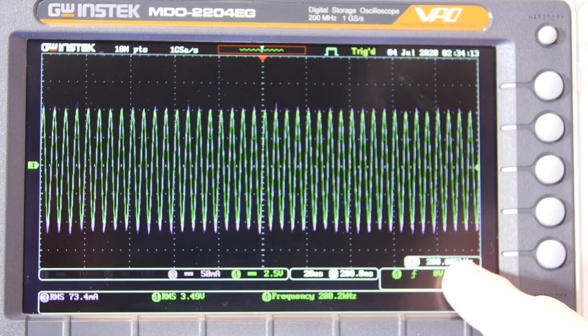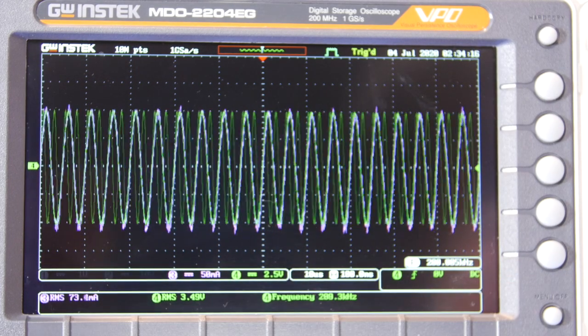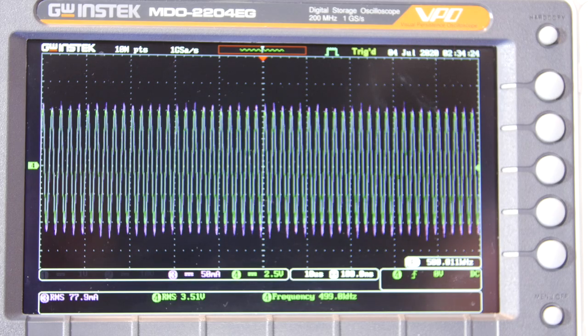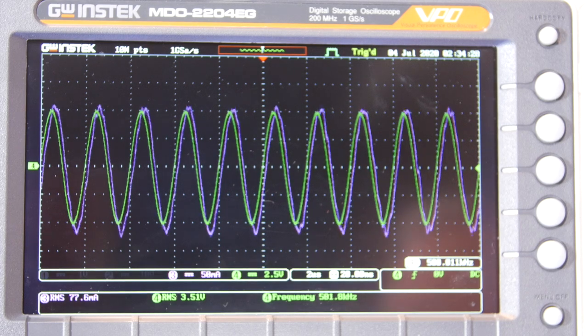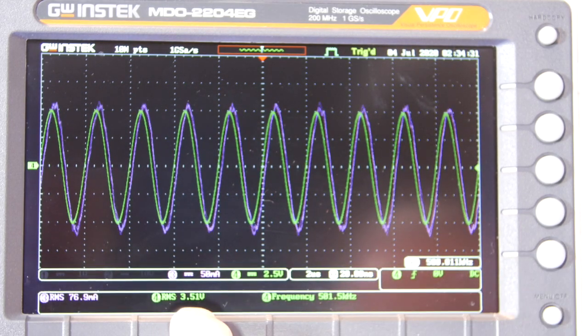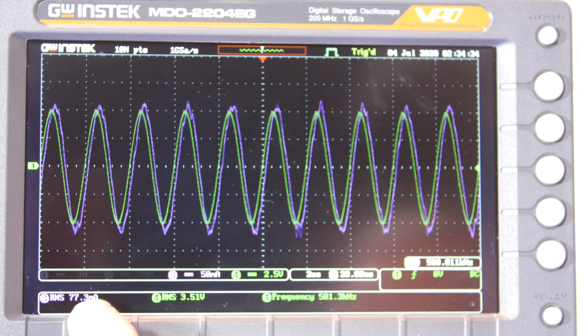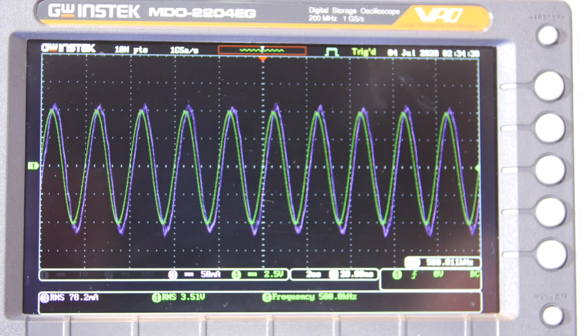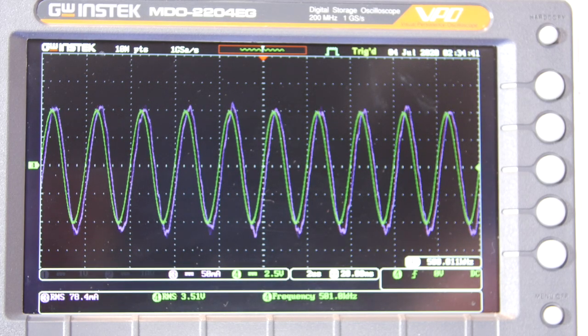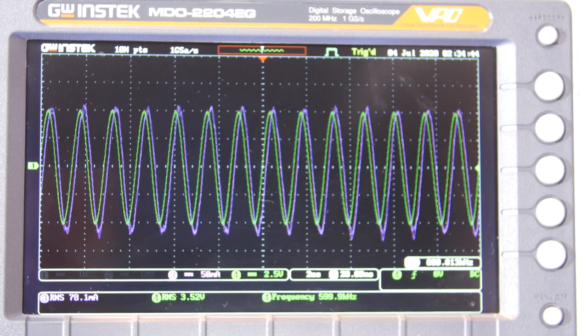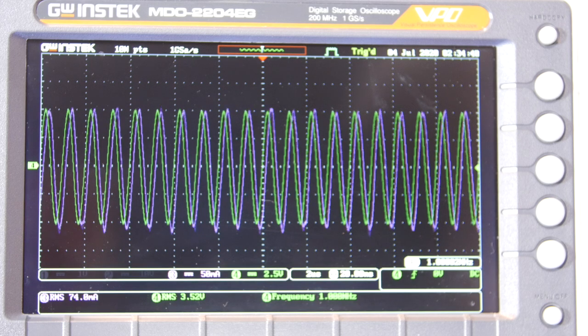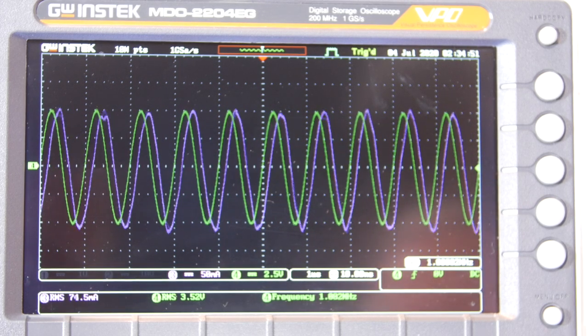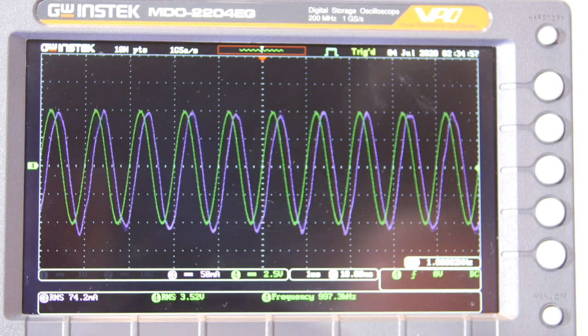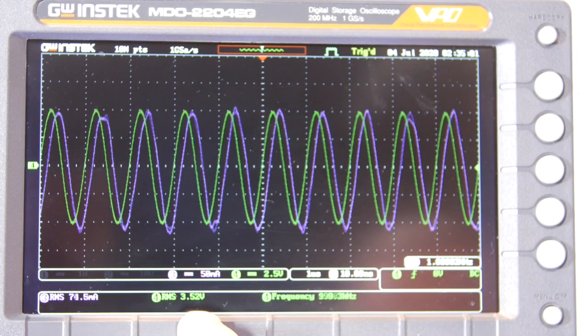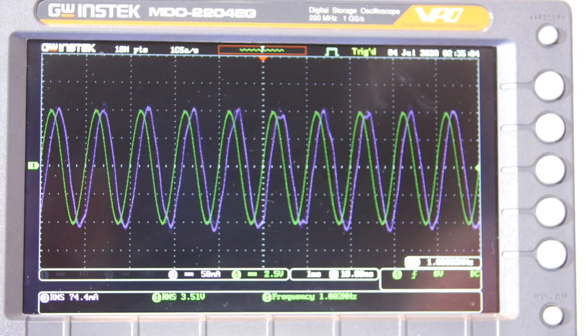So there's 200K. Still a really good reading. Okay, I'm going to go 500K. Look at that, 500 kilohertz, 3.51, 77 point, it's jumping around, 77.5 or whatever. So, man, impressive. Okay, let's go to 1 megahertz. I'm impressed. 1 megahertz on this probe that's less than $1,000. Look at that. 73 point, it's kind of bouncing around, let's say 73.5, 3.52, and you can see 1 megahertz here.